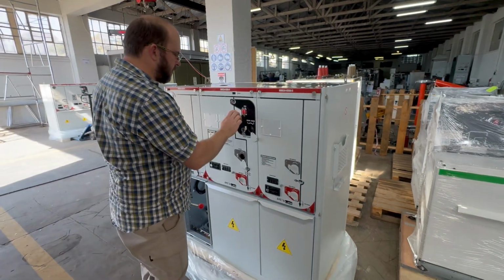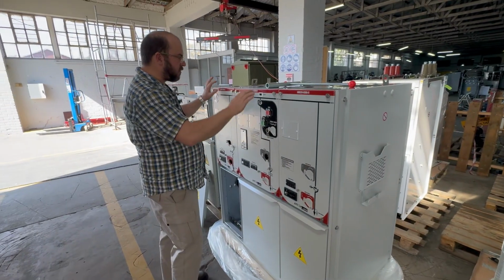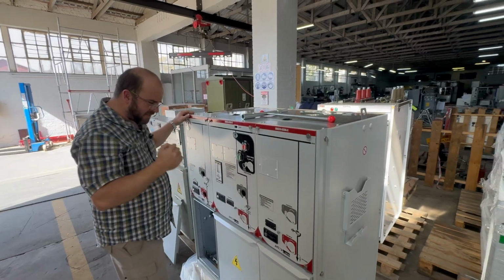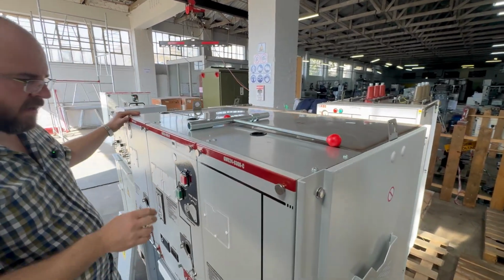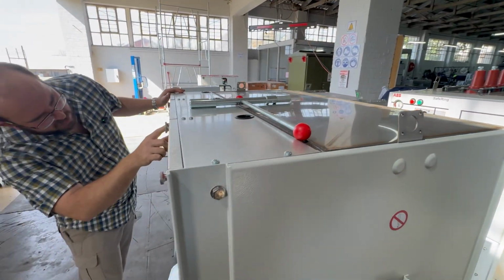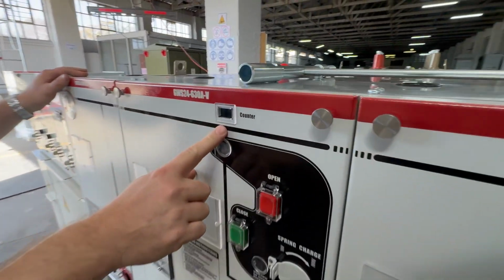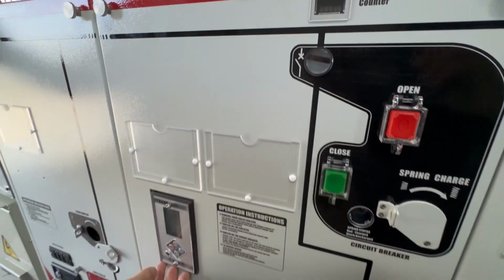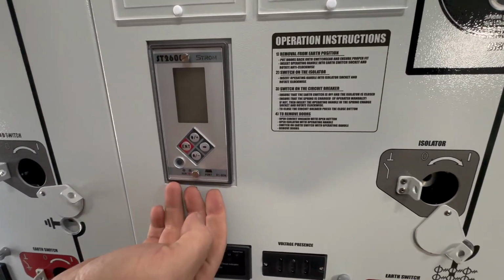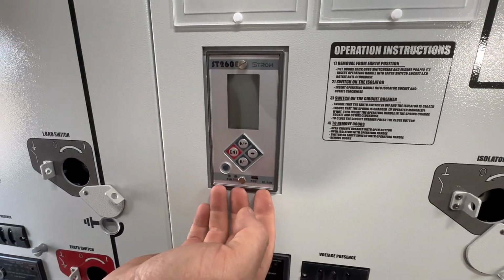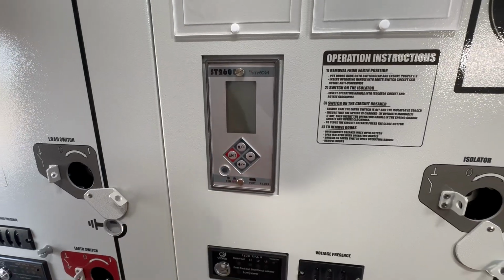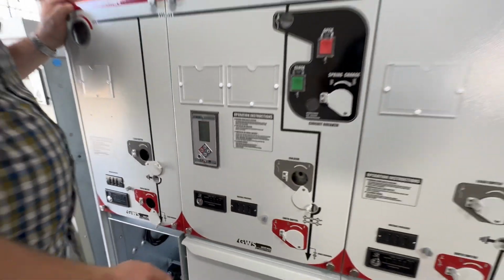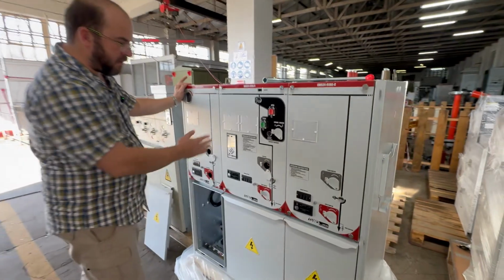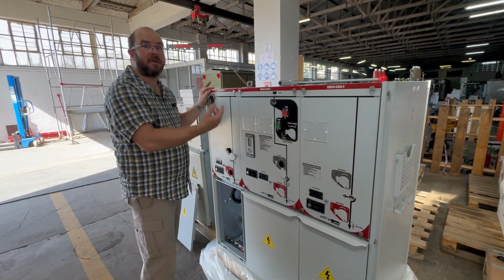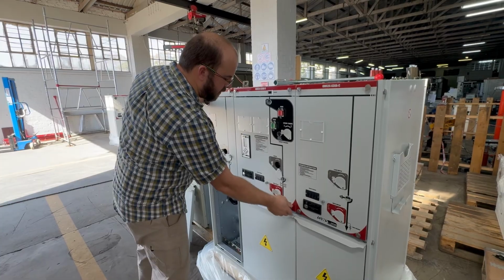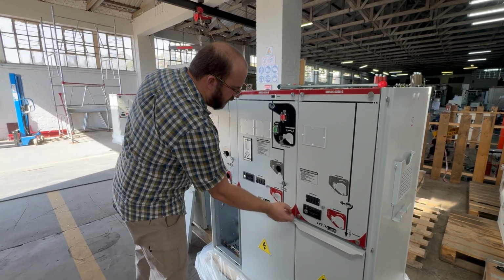Let me show you what goes on inside. So this whole switchgear is very sturdy. You can feel it's steel plates. There's nothing plastic here except for a few covers. You also have the counter at the front, which is something you don't see in many cases. And then you have got your self-powered relay, which is very fast. Even at 30% of the CT rated, it can open in 0.08 seconds, which is not even a 0.1 of a second. So that is on self-powered. When you do power it, it can even be faster, 20 milliseconds. So that's even faster. Let me show you what is on the inside.